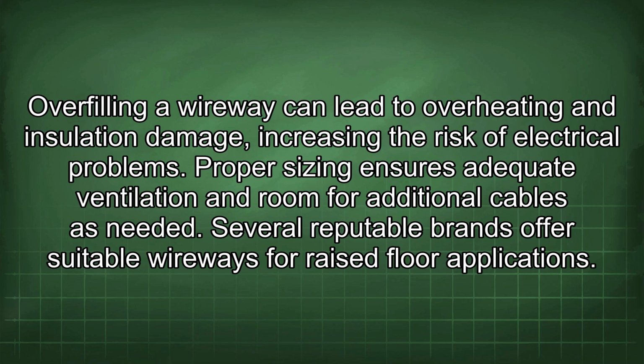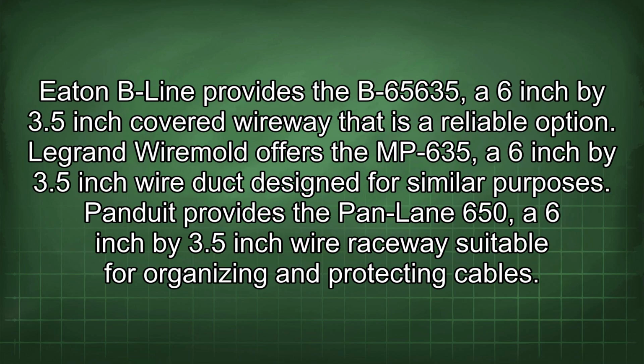Several reputable brands offer suitable wireways for raised floor applications. Eaton B-Line provides the B-65635, a 6-inch by 3.5-inch covered wireway that is a reliable option. Legrand Wiremold offers the MP-635, a 6-inch by 3.5-inch wire duct designed for similar purposes. Panduit provides the Panduct 650, a 6-inch by 3.5-inch wire raceway suitable for organizing and protecting cables.